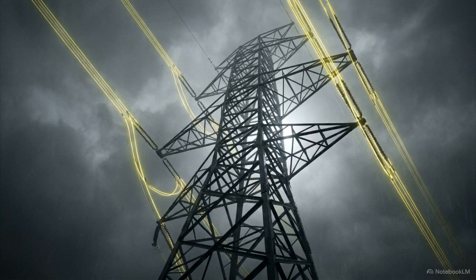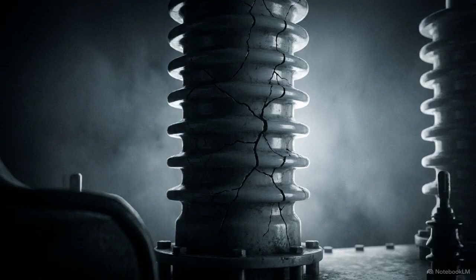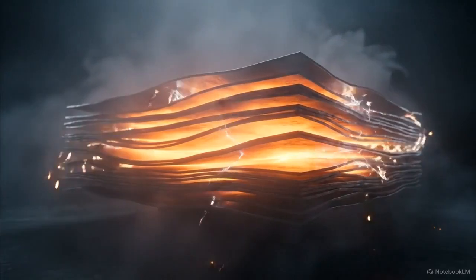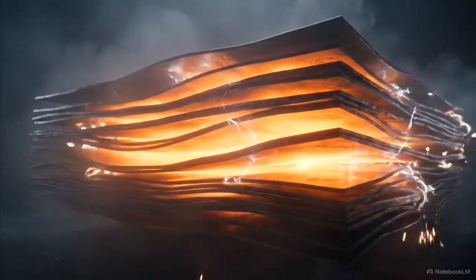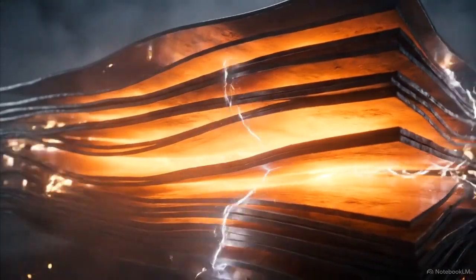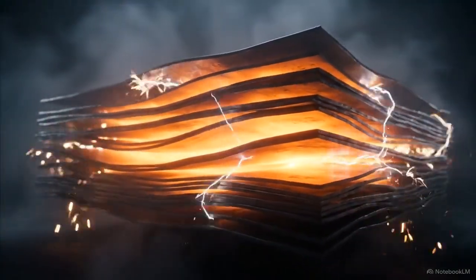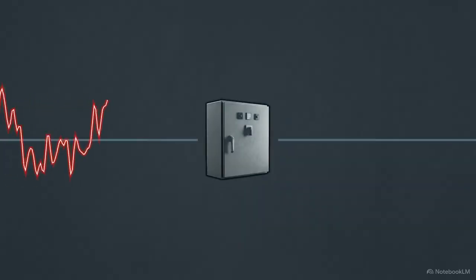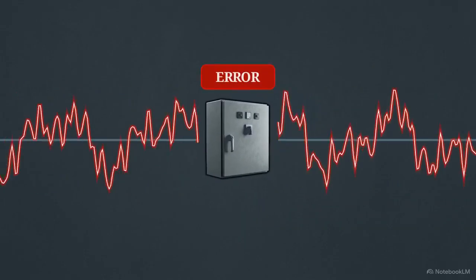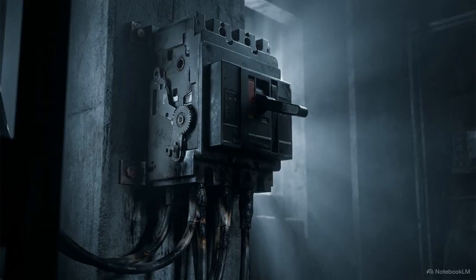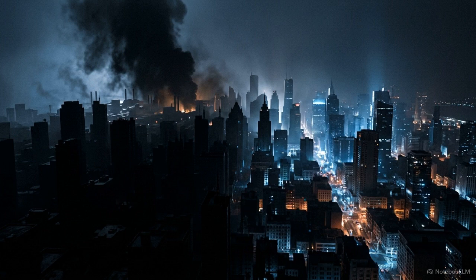Once ferroresonance takes hold, the resulting temporary overvoltages can last for seconds, or even minutes, inflicting stress on the local grid infrastructure. The unpredictable frequencies and sustained high currents generate intense heat inside the transformer. This thermal stress degrades the insulation and warps the metallic core. Making matters worse, the distorted shape of the waveform can confuse standard protective relays. These safety devices rely on clean, predictable signals to know when to trip, meaning ferroresonance can effectively blind them, leaving the circuit live. Left unchecked, this thermal runaway ruins substation transformers and destroys surge arresters, leading to prolonged, widespread blackouts.